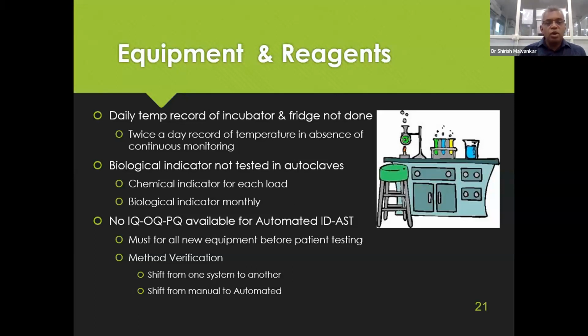Biological indicators not tested for autoclaves. It is advisable that chemical indicators go in with each load of autoclave that you run, and a biological indicator should be run monthly. It is mandatory by law, if you look up the biomedical waste guidelines, that you maintain a record of these indicators, the chemical indicators with each load and the biological indicators monthly. It needs to be maintained.